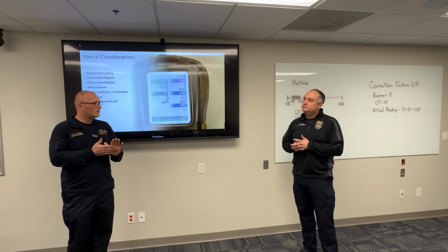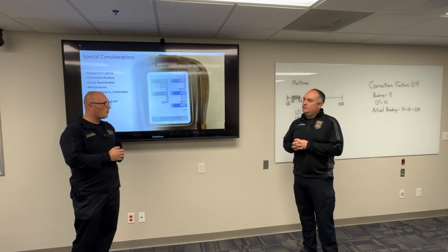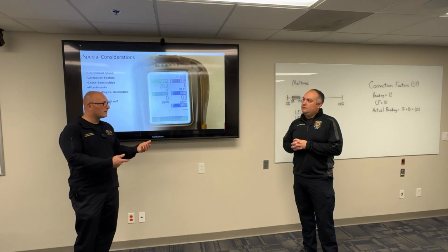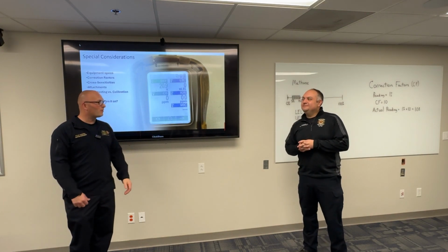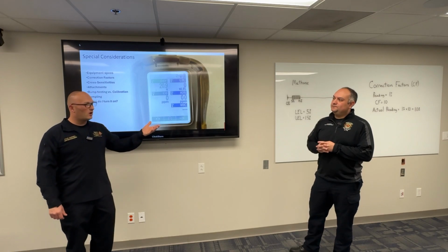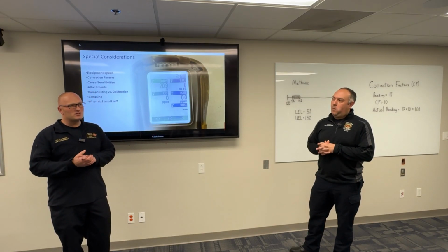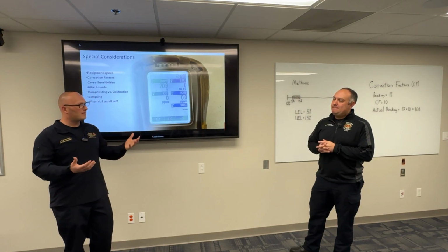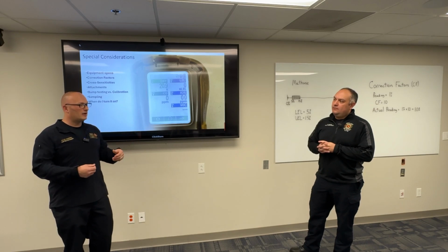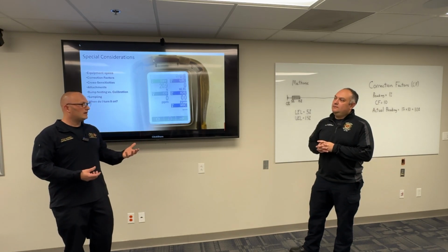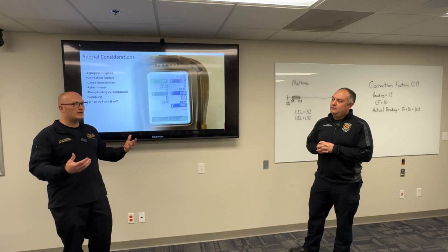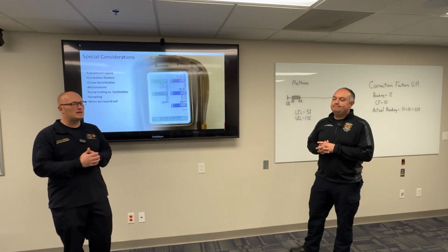I know ours is, there's a lot of times I'll get off the truck, be talking to the homeowner, and the back step's still sitting there like, no, give me a minute, we're still warming up, or they had to do a fresh air calibration. So a lot of times we turn them on in the truck on the way there. Something to be cognizant of: if you did have that fire, your gear's in there, gear might still be off gassing, and now I'm turning this thing on inside the cab of the truck, and it's trying to do a fresh air calibration while your gear's off gassing. So that's just something else to keep in mind.